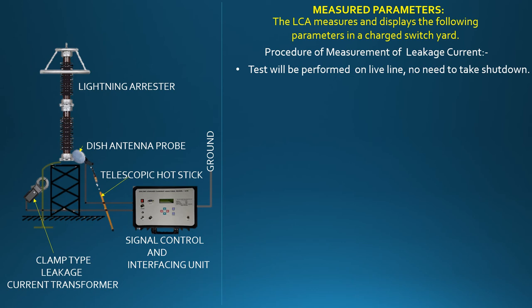First, ground the signal control and interfacing unit. Connect the clamp and dish antenna probe with the measuring instrument. Place the clamp as shown in the picture, and place the probe at or near the base of the lightning arrester to be measured using the hot stick, and leave it untouched. Start testing. The results will be displayed directly on the screen of the measuring instrument.